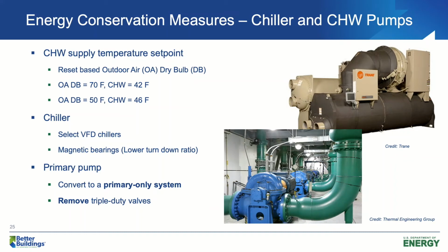Remove all your triple duty valves. Triple duty valves can do three things: balancing, check valves and shut-off valves, but typically we use triple duty valves only for balancing purposes. If we have VFDs on our pumps, we do not need triple duty valves to do the balancing job. We can just use the VFDs to do the system balancing. By removing those triple duty valves, we can save a lot of pump energy because triple duty valves have a lot of pressure loss.